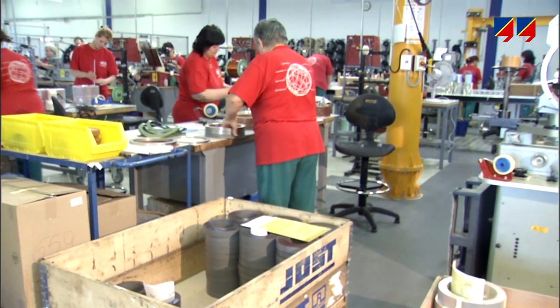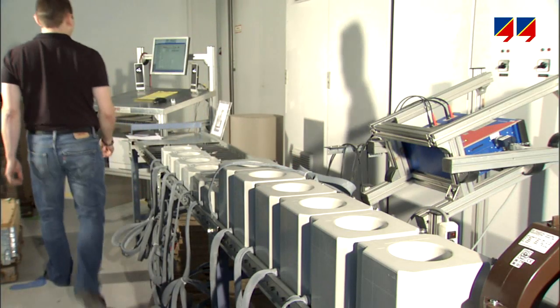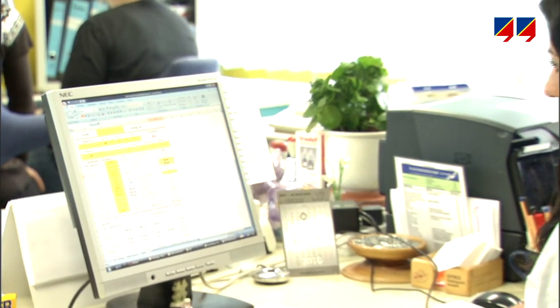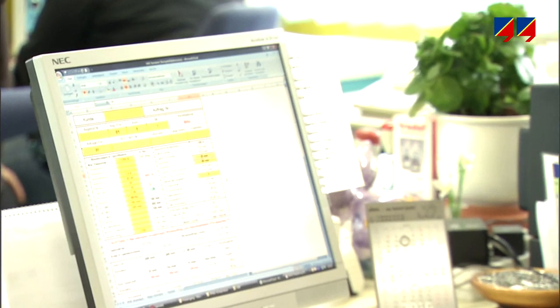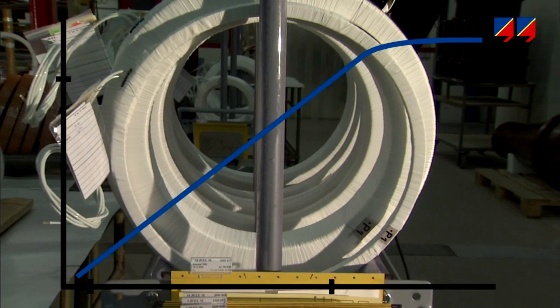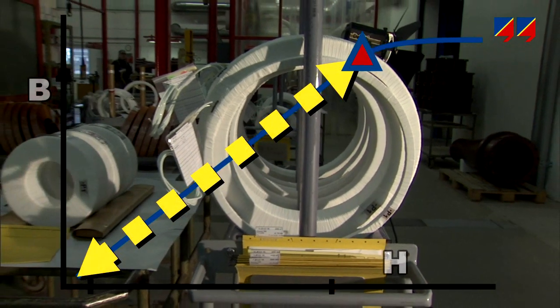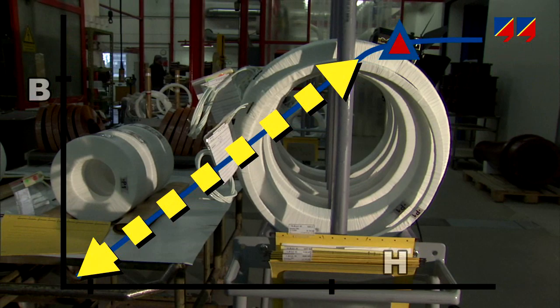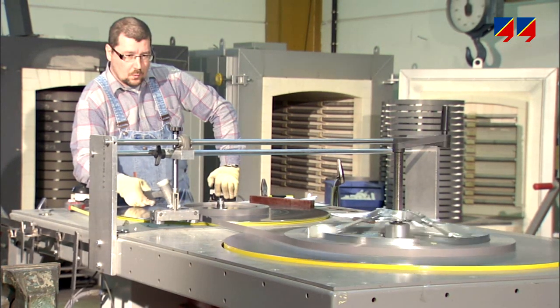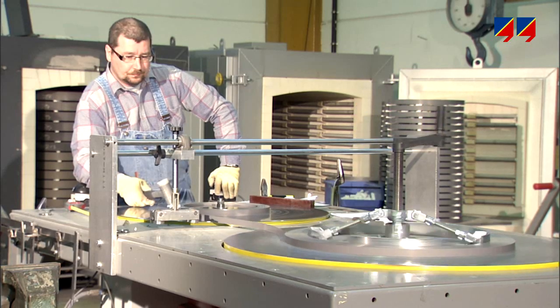CT manufacturers have to produce CTs fulfilling these parameters and verify them through testing. The first step is the design of the CT, where core and winding geometry and material are defined using numerical calculation tools. Regarding protection CTs, the core must allow the generation of sufficient terminal voltage to feed many times the nominal current into the burden comprising the protection system. For metering CTs, it has to ensure high accuracy within the operating range and must saturate for currents slightly above it. Sometimes this can only be achieved by combining different core elements consisting of different magnetic materials.